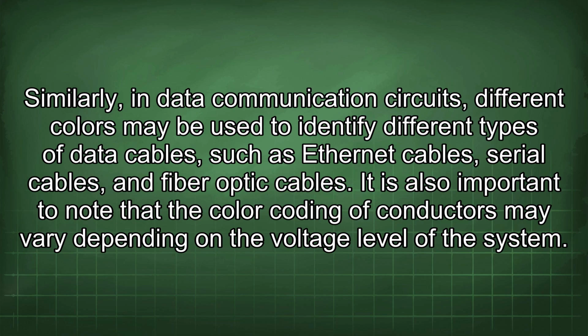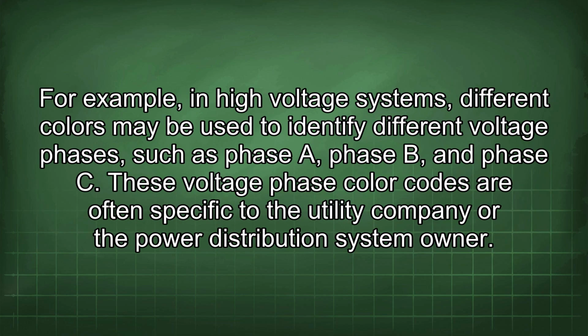It is also important to note that the color coding of conductors may vary depending on the voltage level of the system. For example, in high voltage systems, different colors may be used to identify different voltage phases, such as phase A, phase B, and phase C. These voltage phase color codes are often specific to the utility company or the power distribution system owner.